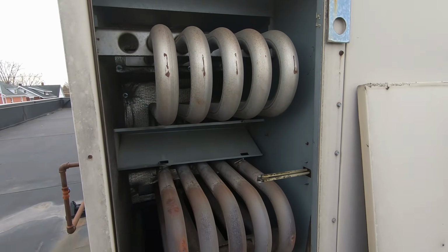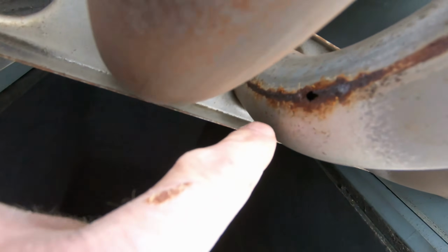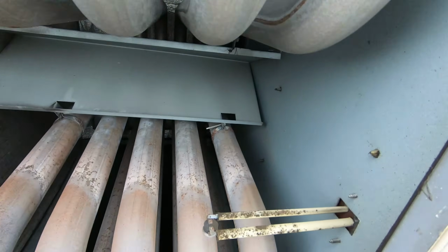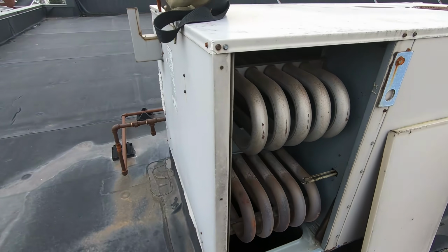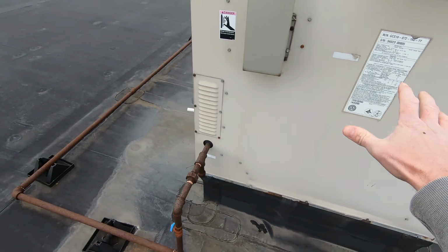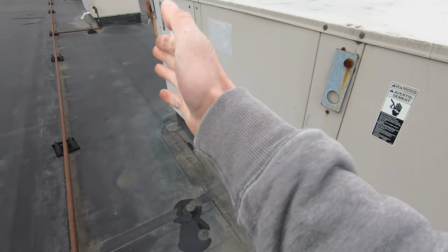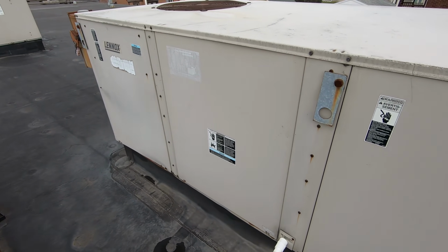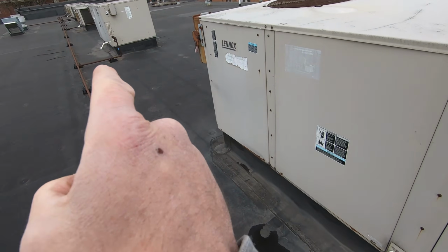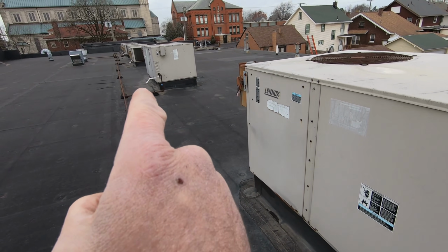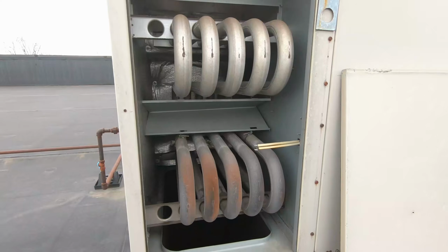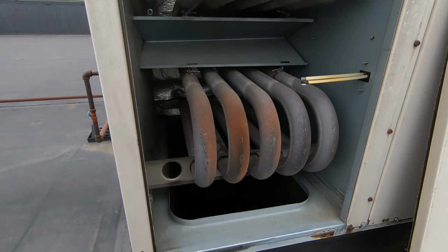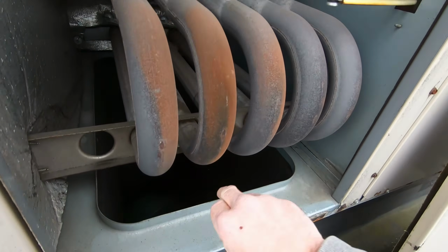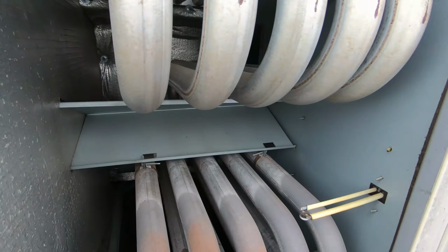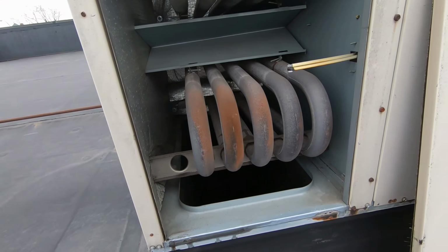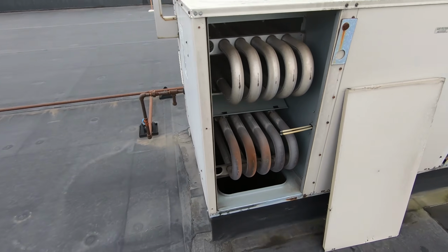All right, well, first things first, we got a hole. So this one's got a bad combustion blower. I could hear it, so right off the bat it's gonna get a heat exchanger and all new heating parts. We'll look at the electrical, we'll look at the blower, make sure there's no other issues with that. But in the meantime, I'm gonna go see why we don't have electric to this unit and also check its heat exchanger. All right, well, this heat exchanger appears to be okay. Some of the seams are rusty, but nothing's poked through. So let's dig in and see what is going on with the electrical, see if we have any power.